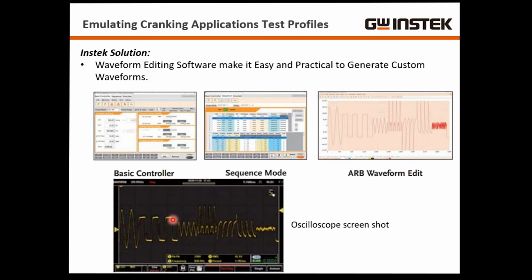It allows for a lot of variety in terms of your signal and how you can actually output it. So it's very versatile when it comes to the types of signals you want to put out. Now, as I said before, on our test scripts and our DC power supplies, we can go up to about 100 milliseconds. With this one, you can go to 100 microseconds. So it's a lot faster, it's a lot more practical. It's just as easy as testing test scripts, but it allows for this type of testing.